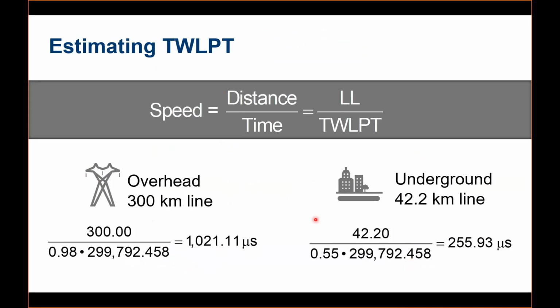Now there is one more parameter that we call the traveling wave line propagation delay. This is very important. If we have this value, we can find the time reference, and we can exchange some information between two end relays to get a lot of things out of it. Maybe traveling wave fault location or differential protection. So the traveling wave line propagation delay is kind of a fixed parameter. It is defined as the time taken by a traveling wave to travel from one end of the feeder to the other end.